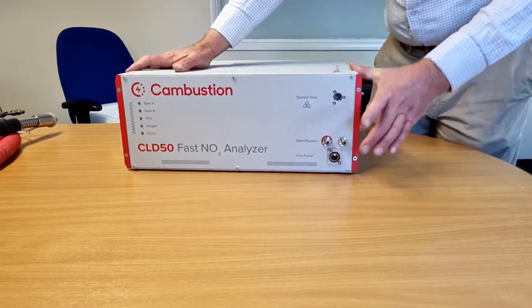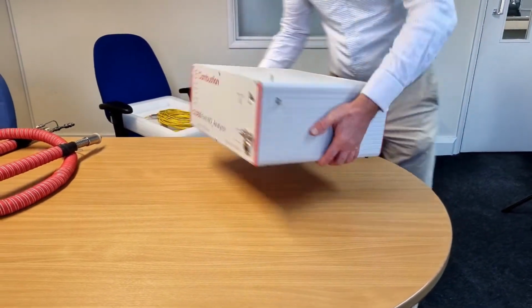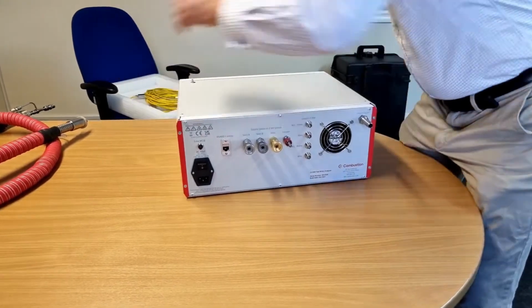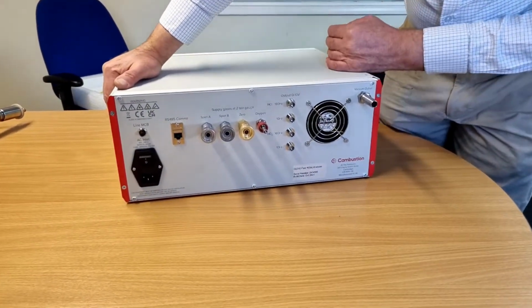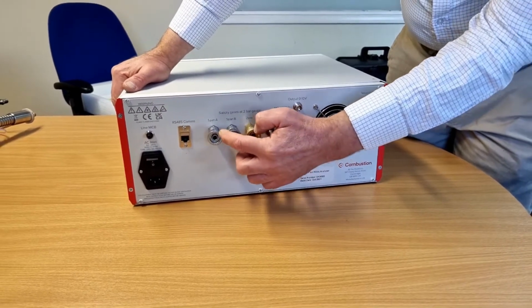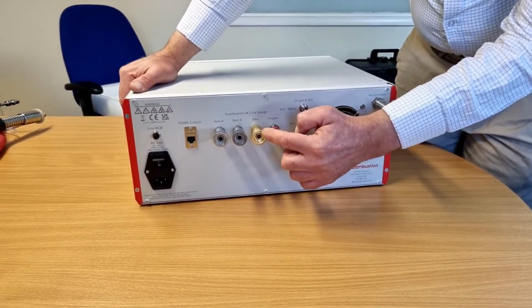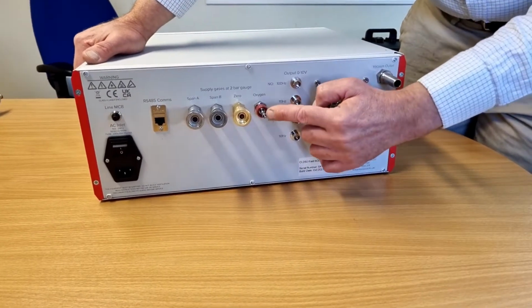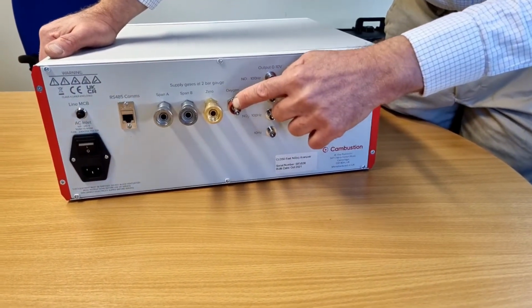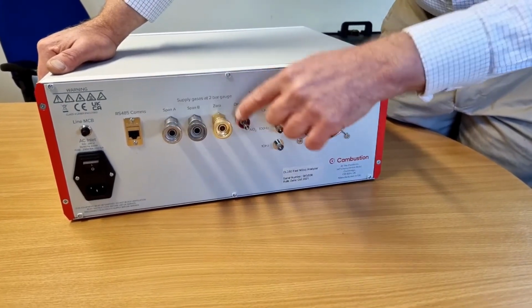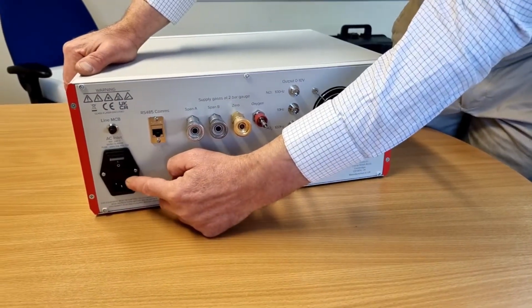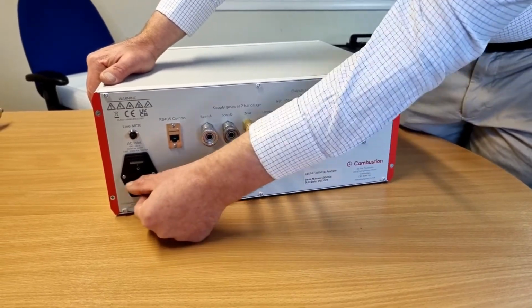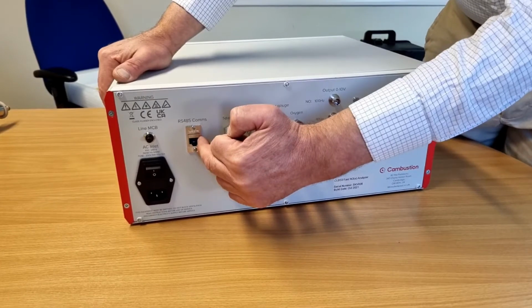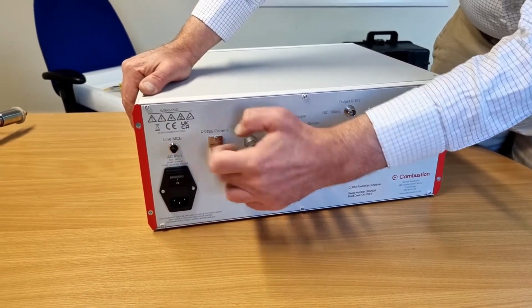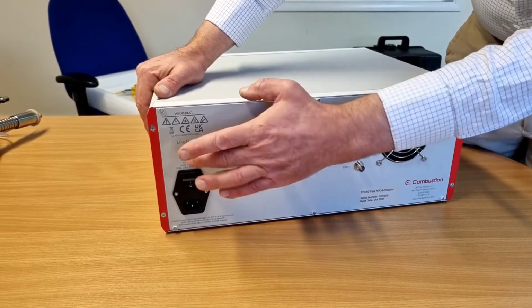If I turn the analyzer around, on the rear we have a selection of gas inlets for 2 different types of calibration gas if required. Zero, that's generally nitrogen, and oxygen inlet. And the reason that that's a different style of connector is so that you can't get them mixed up. Here's our mains power inlet with a switch, and there's a fuse in here as well. This is where our RS485 communications connects. This is a circuit breaker which pops out if the heated sample line has a short circuit.